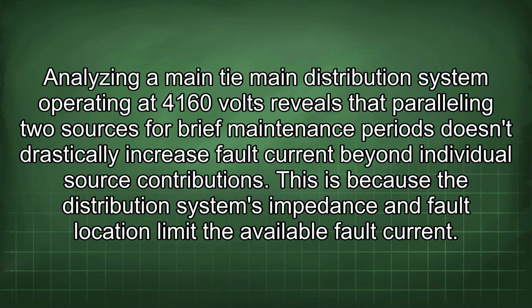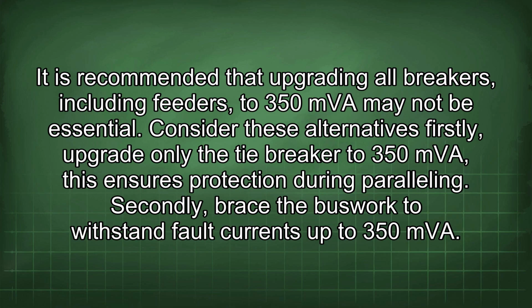Analyzing a main tie main distribution system operating at 4160 volts reveals that paralleling two sources for brief maintenance periods doesn't drastically increase fault current beyond individual source contributions. This is because the distribution system's impedance and fault location limit the available fault current. It is recommended that upgrading all breakers, including feeders, to 350 MVA may not be essential.